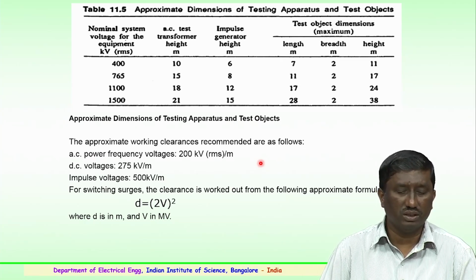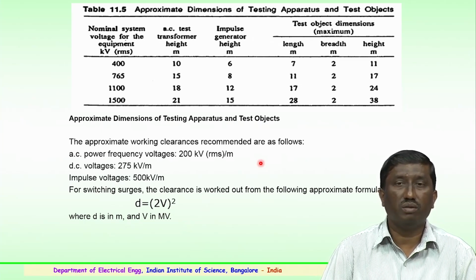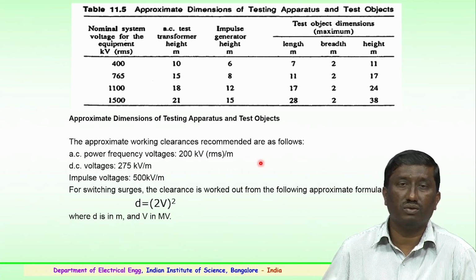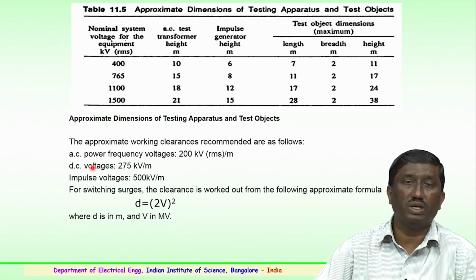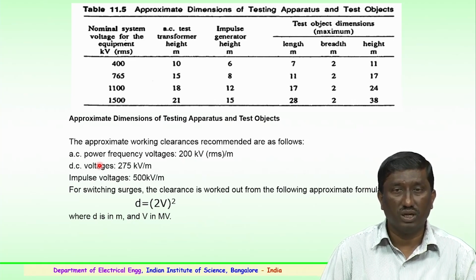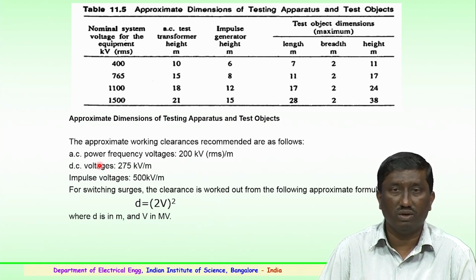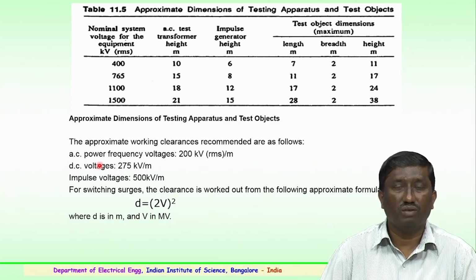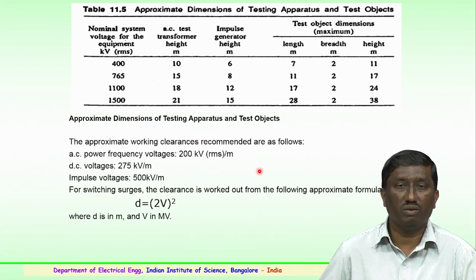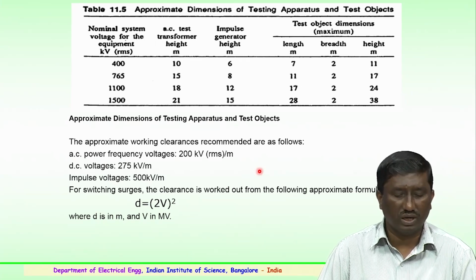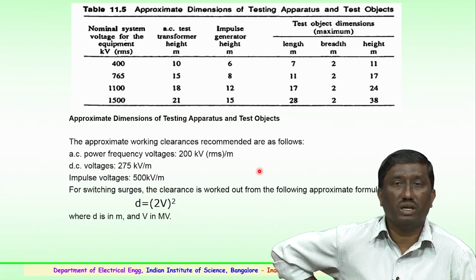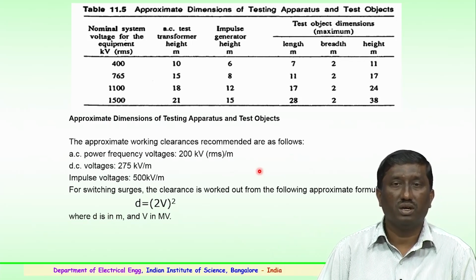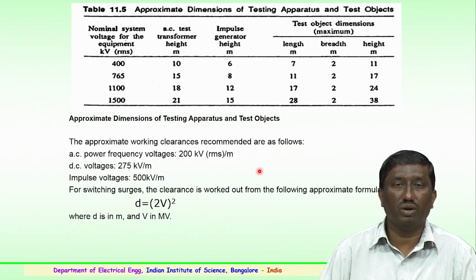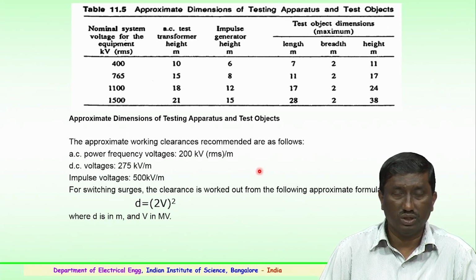The approximate working clearances normally recommended for laboratories are as follows. For AC, that is 50 hertz power frequency voltages, as a thumb rule it is taken as 200 kV RMS per meter, and for DC voltages 275 kV per meter. For impulse it is 500 kV per meter. These are the minimum distances to be maintained: AC 200 kV per meter, DC 275 kV per meter, and impulse voltages 500 kV per meter.